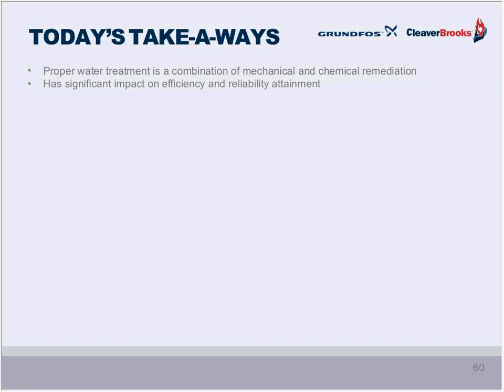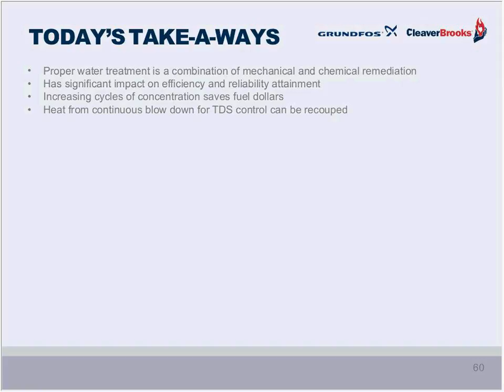Let me just give everyone what Jared and I thought would be the good takeaways. Proper treatment is a combination of mechanical and chemical remediation, as I took you through. Chemical treatment has a significant impact on efficiency and reliability within that total system. Increasing cycles of concentration saves fuel dollars. That means the more you concentrate those impurities in the boiler feed water, the more you have to blow it down, which would be continuous blowdown. Heat from continuous blowdown or TDS control can be recouped. Proper and reliable chemical dosing is paramount for assuring steam boiler system reliability and life.